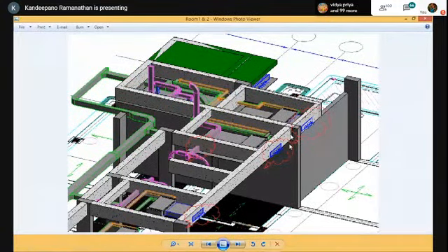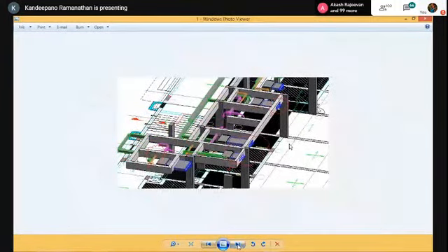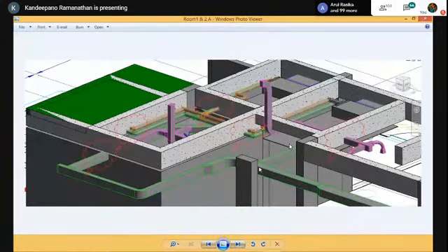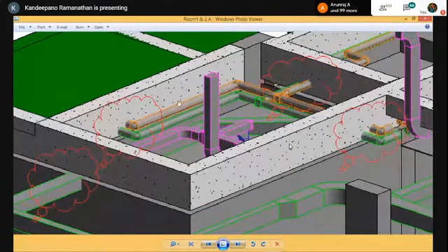Definitely structural engineers will not allow such a big opening in the concrete beam. But this is identified by this Revit 3D drawing. A 2D drawing is made in Revit software and converted into 3D. It converts it automatically, and these clashes are seen. Now this informs the structural guy who will give a solution by removing this beam or whatever. In fact, he removed the beam in this project. These are the various views. You can see this is a beam here. This is the pipeline coming out.